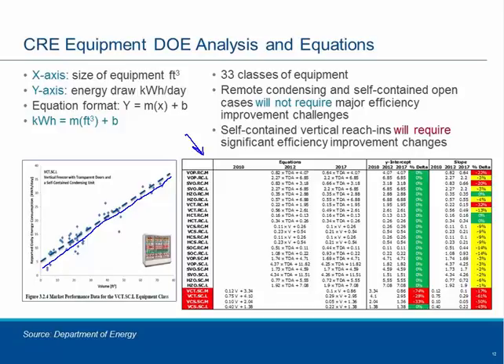As I mentioned, a y-intercept changing would basically, right off the top, tell you where the new baseline energy draws would begin. What I can tell you is that on the vertical opens, a lot of these open display cases, horizontal deli cases, the equations we've had in 2012 and 2017 now don't change that much because the y-intercepts continue to be the same. Here in this case it's 4.07, and then here it's also 4.07 with a slight decrease in the slope. So the implication for the installed base and this industry is that if there are open display cases, deli cases, and these applications are meeting 2012 regulations, not a whole lot needs to change for 2017.